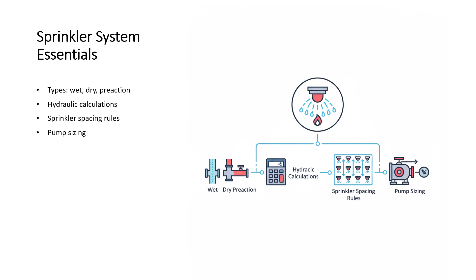Then we do the step of hydraulic calculations, so that the pump used with our system is accurate for our requirement, considering a fire at the most remote area. It must be enough to provide the maximum pressure to our water so it can easily continue suppressing the fire. And then is our spacing rule for sprinklers, that our sprinkler coverage areas must be good so they cover everything. And then is our pump sizing, that is defined in hydraulic calculations.